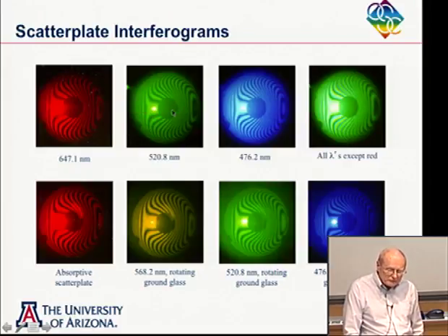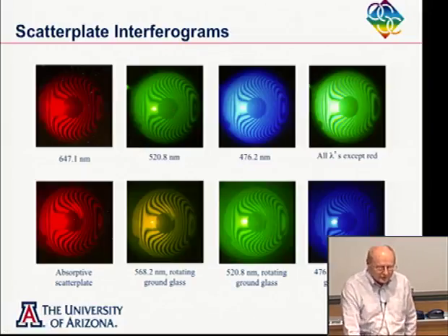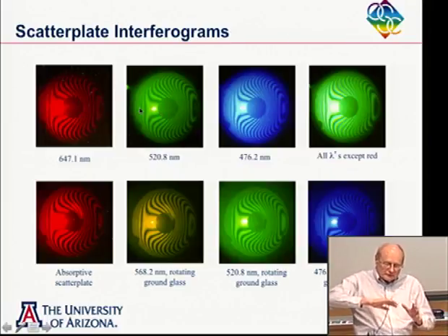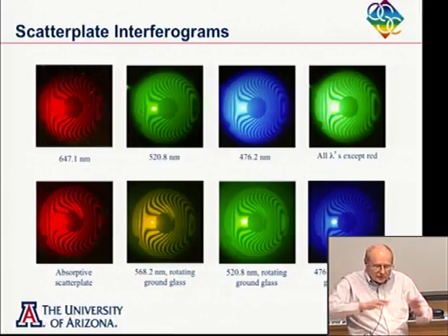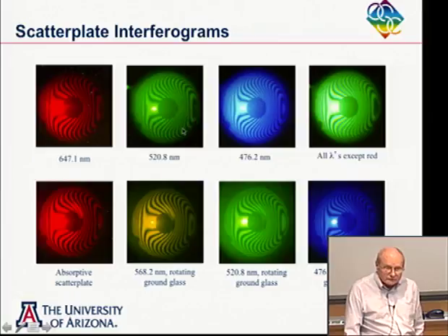I mean, typically, you probably put it in the center. Well, there's a hole in the center, so I can't put it in the center. So you put it close to the center. But it's going to work fine if you put it out here. Just that there's going to be a little drop-off in scattered light as you move away from where the source is focused. So if I put this way over to the edge, I might see more drop-off here. In fact, right now, this is off to the left here, and probably there's a little drop-off in intensity over here on the right.